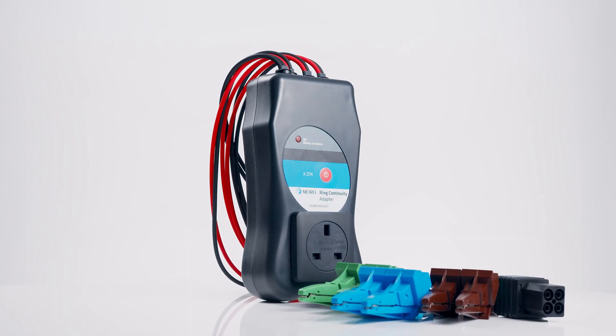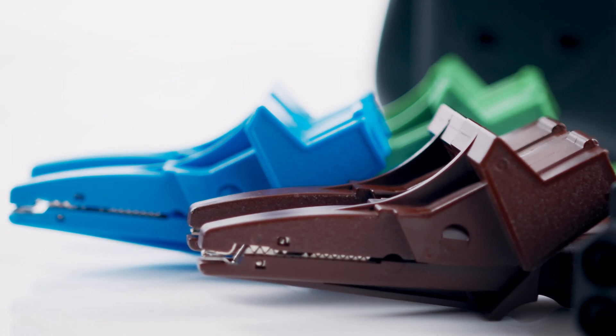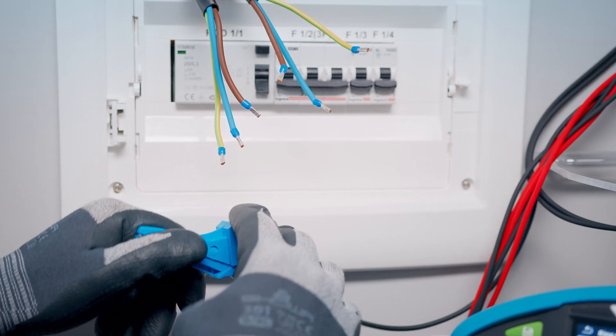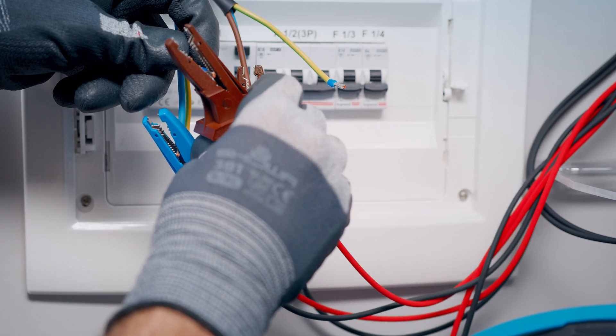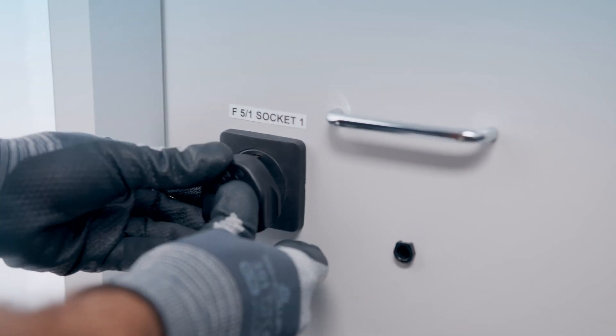The new Ring Continuity Adapter A2214 is Metrel's latest tool for testing continuity of ring final circuits. It is a far cry from the traditional way of testing, which is both time-consuming and fiddly, cutting the testing time by up to 60% and making the procedure simple.